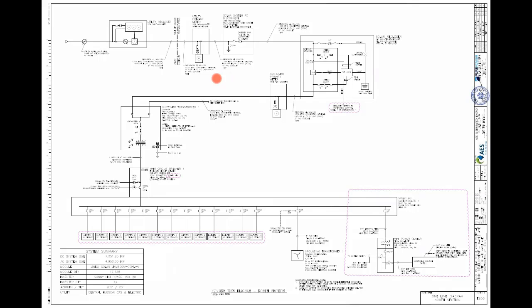This application, this project, has utility primary metering. There's a recloser up on the pole for the utility. There's a fused disconnect switch. We have a solar recloser, a pad-mounted solar based recloser for the solar application, that is. I think John touched on that. At times they don't want to have that recloser up on a pole, so they'll do a pad mount enclosure instead. You have customer primary metering.